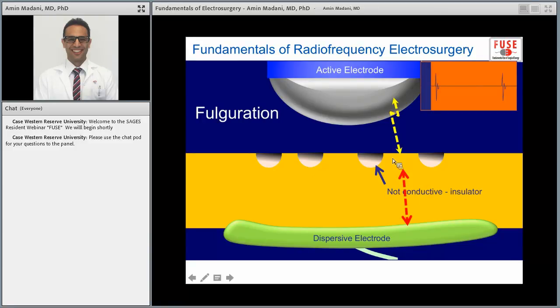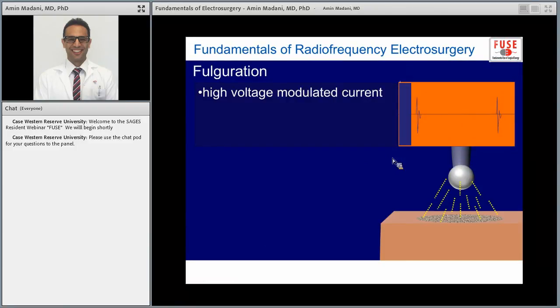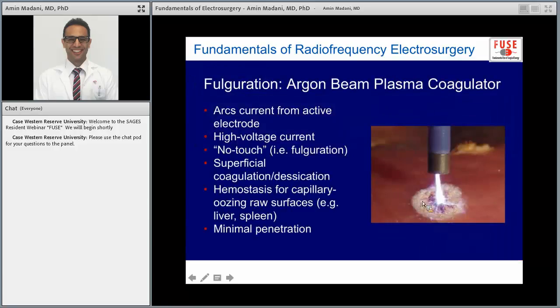And this is really good for situations when you have raw surfaces that are bleeding. So again, high voltage modulated current, no touch technique, and it's usually better when you have a larger surface area electrode to do this. And the good thing about this is, like I said, if you have liver or spleen, you want minimal penetration, you really want to coagulate a raw surface that's bleeding, and this is really a good technique to use. And in fact, argon beam plasma coagulation actually uses this form of energy, this form of tissue effect by fulgurating the tissue.